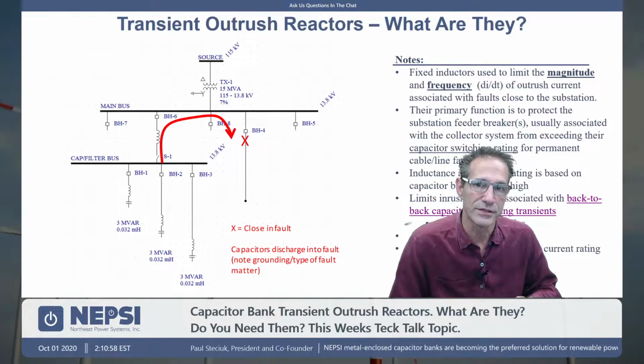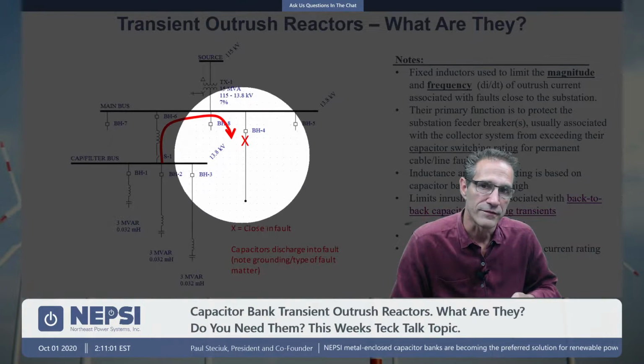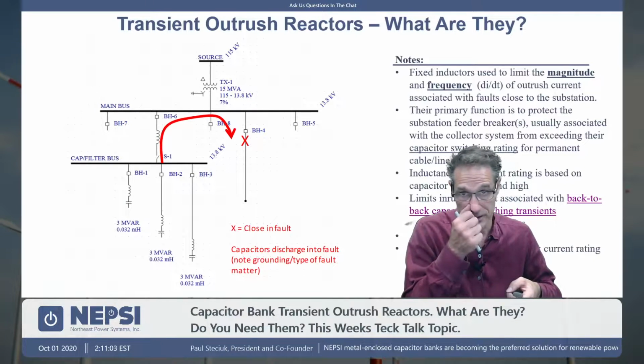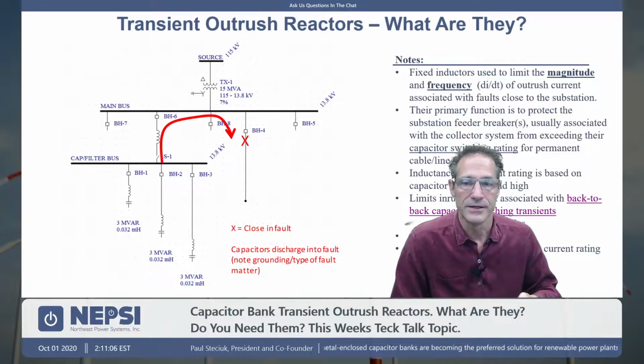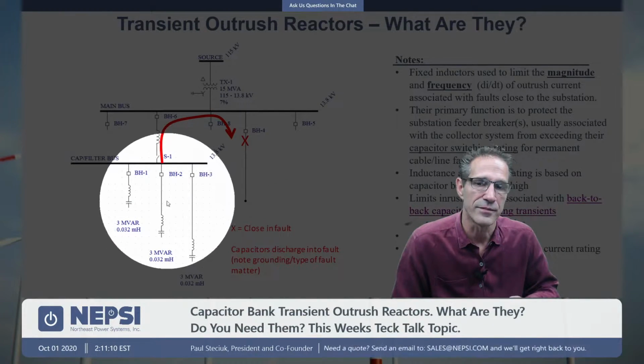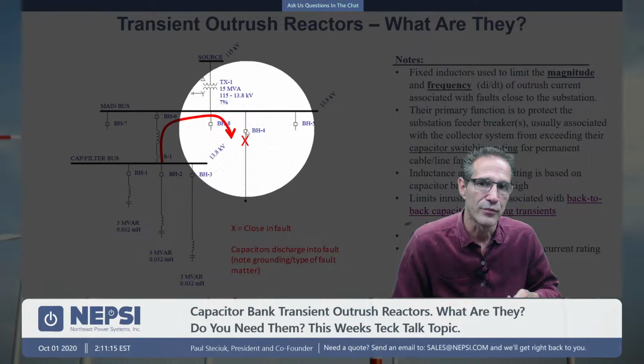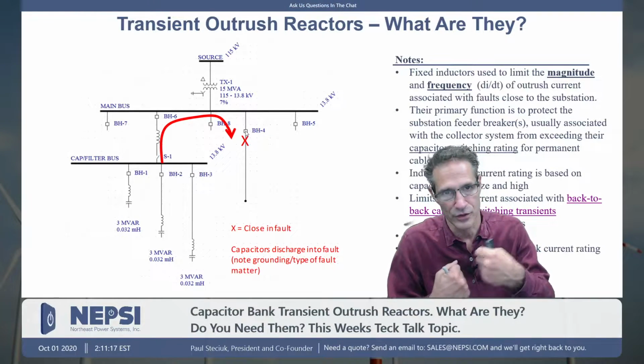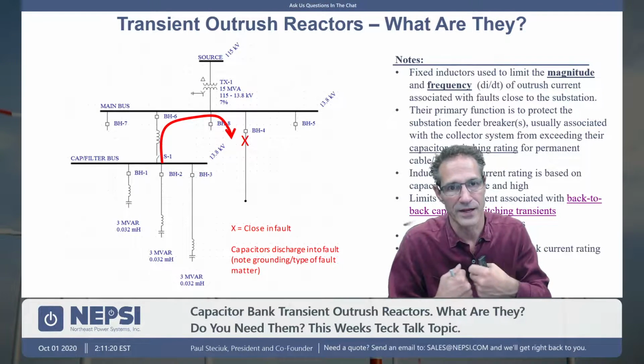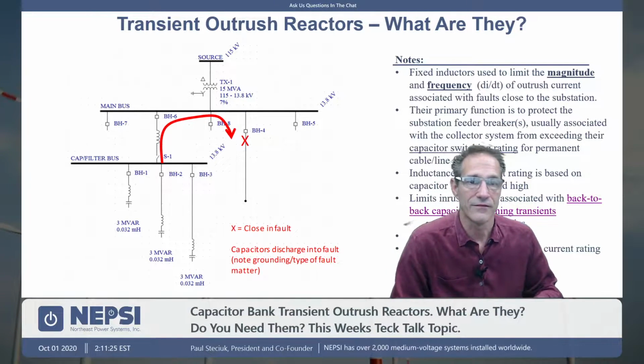Now in that situation, if there was a permanent fault, if that X represented a permanent fault, say he didn't locate that fault and it was permanent, the charge that exists on these capacitor banks will want to discharge into that faulted condition. And that breaker, more or less, now is making the current. It's actually almost like a back-to-back transient situation. It's actually making a transient, making current. In fact, the formulas to calculate this current are the same. And so that's what the situation is.